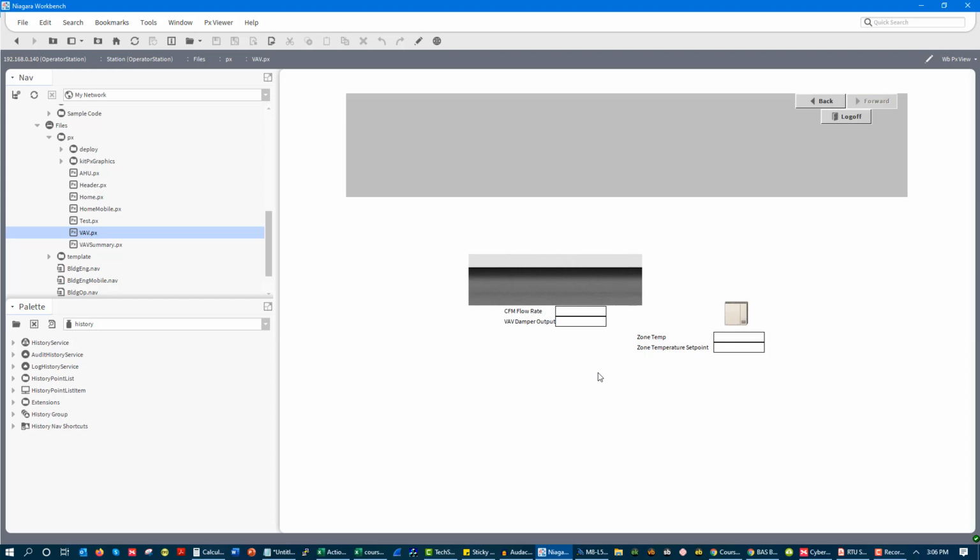The problem with template graphics, especially if you're a building operator and you change things, is this: let's say you're using a VAV template graphic, but then you have a space that you need to do a dehumidification sequence in. So you add reheat and you say, I'm going to subcool the space and then heat the air back up, kind of do some dehumidification. Well, now you have a reheat valve you've got to add to this.